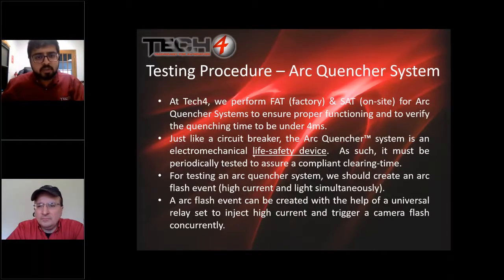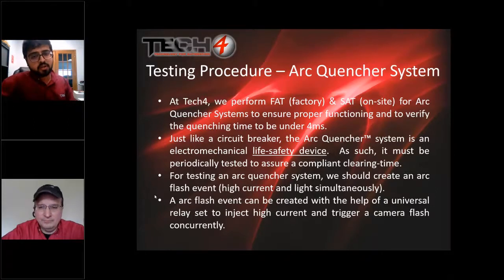Also, like Mike Bukowicz was explaining, it's a life safety device, and it's better to periodically test the arc quencher, just as you test your circuit breakers as well. So for testing the arc quencher system, we have to create an arc flash event, injecting a high current, and also probably use a camera flash in this case for the flash. So a light plus current initiation would send a trip signal from the protection relay to the quencher, and the quencher quenches.